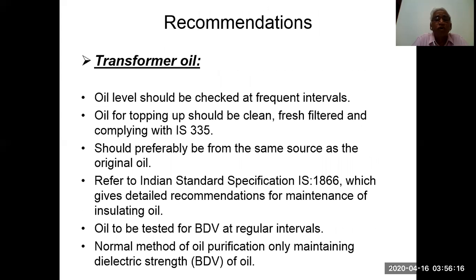Recommendations: transformer oil. Oil level should be checked at frequent intervals. Oil for topping up should be clean, fresh, filtered, and comply with IS 335. It should be preferably from the same source as the original oil. Refer to Indian standard specifications IS 1866, which gives detailed recommendations for maintenance of insulating oil. Oil to be tested for BDV at regular intervals. Normal method of oil purification, oil maintaining, and dielectric strength.